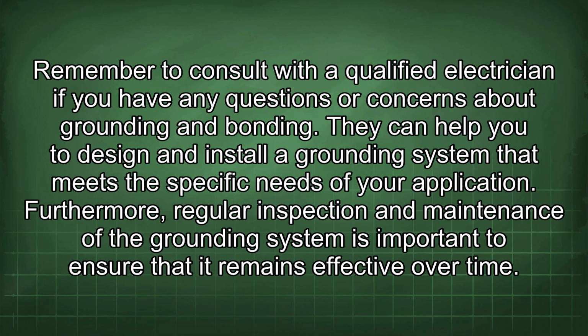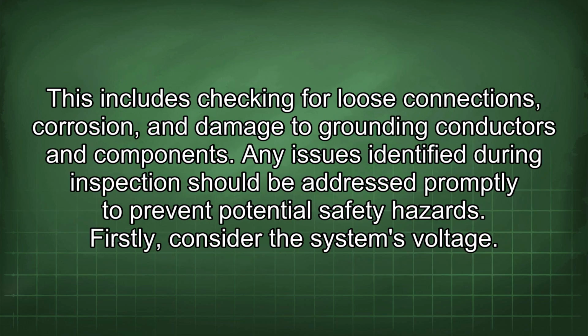Furthermore, regular inspection and maintenance of the grounding system is important to ensure that it remains effective over time. This includes checking for loose connections, corrosion, and damage to grounding conductors and components. Any issues identified during inspection should be addressed promptly to prevent potential safety hazards.